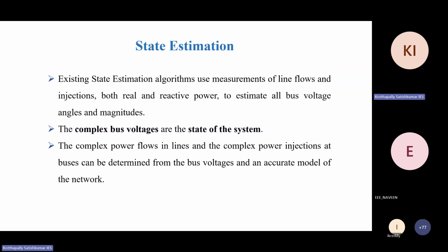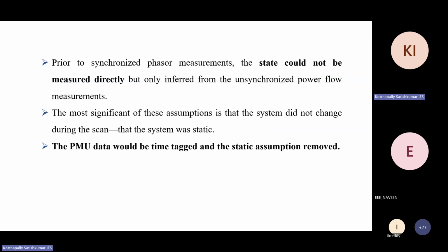So the difference between state estimation with the conventional system and with PMUs is this: in the conventional one, you run all these mathematical equations iteratively to get an accurate result. Whereas with PMU, you directly measure the state of the system. So there is no iterative process. It's a simple linear problem, directly solved. Prior to synchronized phasors, the state could not be measured directly, but because of the PMU, now you can measure the state of the system directly.